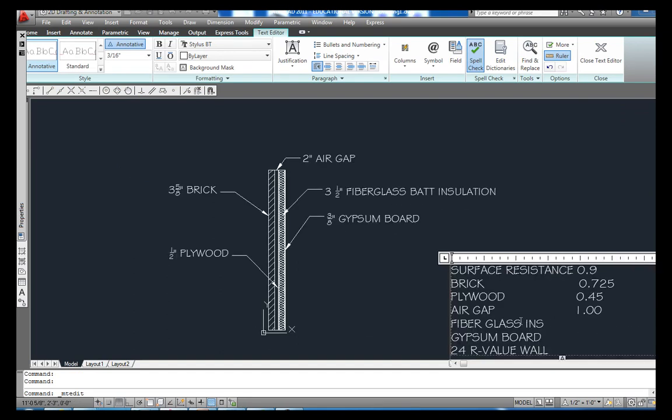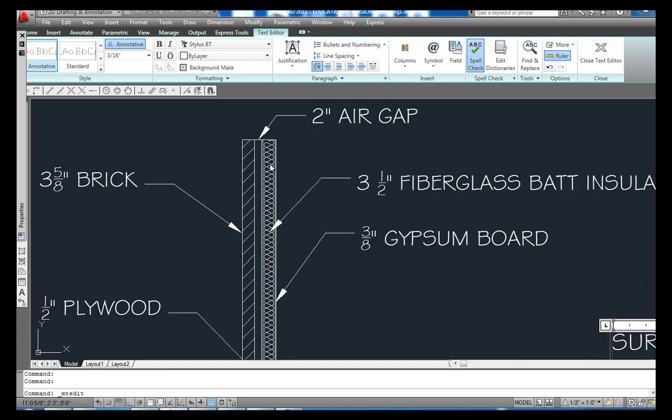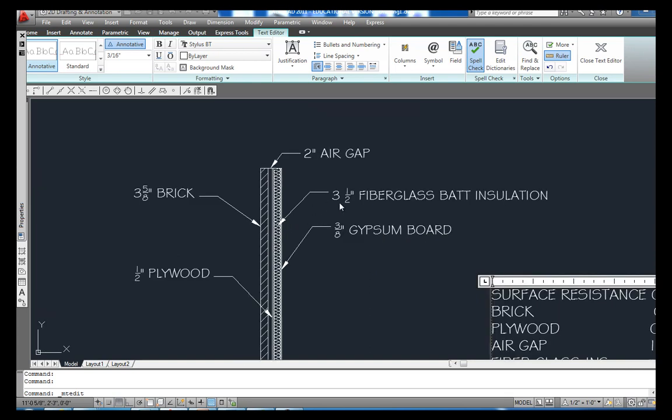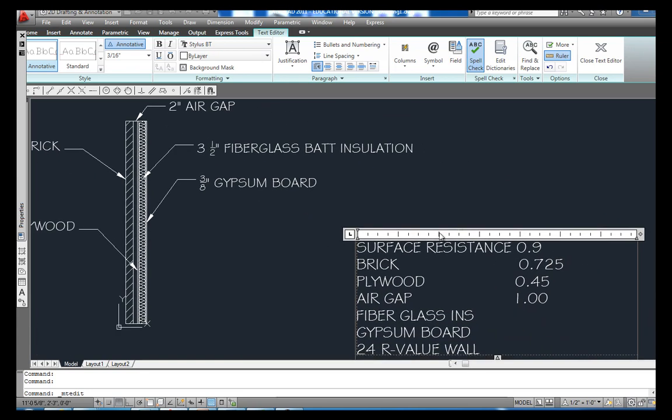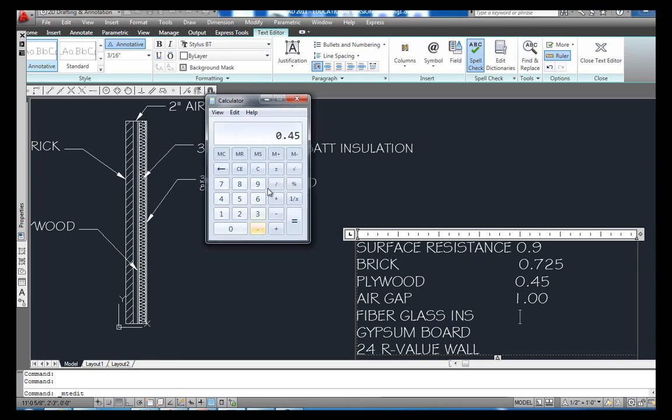Okay, now here's where your R-value is going to really grow is this fiberglass insulation. And you look up here, it's a batt insulation, and this right here's the symbol for it in a section view. And we're using two by four which is three and a half inch actual size, and the fiberglass is in there. Let's look that up. Fiberglass batt or blanket insulation has a R-value of 3.5. So 3.5 times 3.5, which is our stud wall, is going to be 12.25.